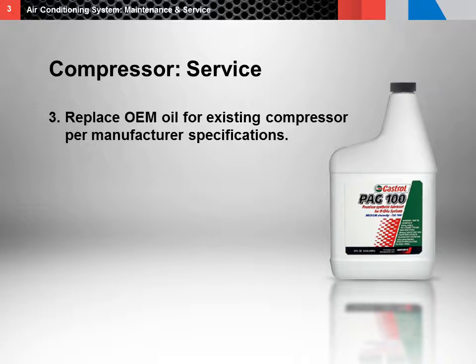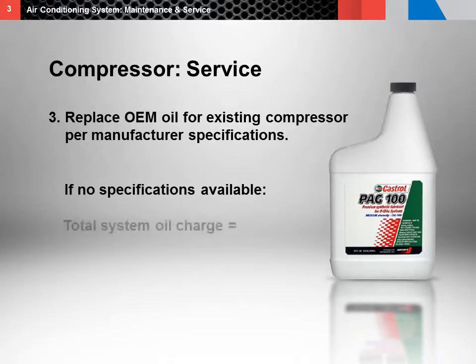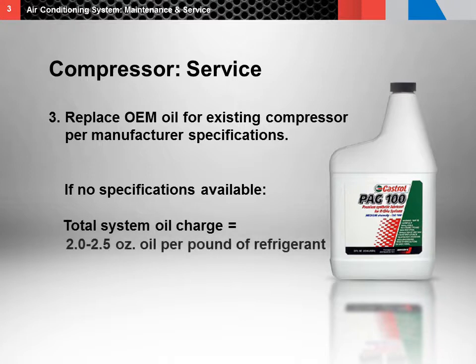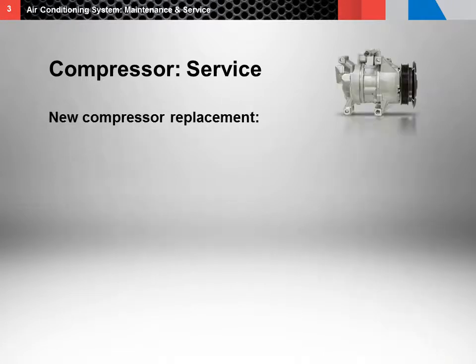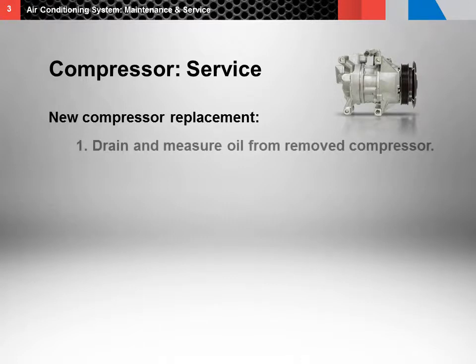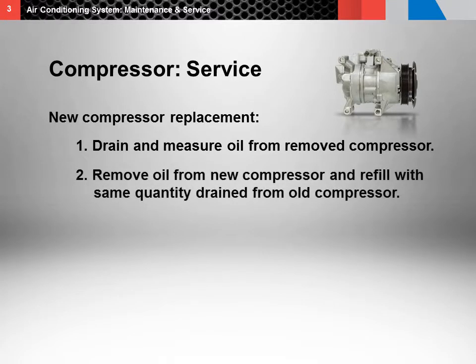The correct amount of oil to add should meet the OEM specifications. If there are no specifications available, the total oil system charge should be two to two and a half ounces for every pound of refrigerant in the system. When replacing an old compressor with a new one, drain and measure the oil from the removed compressor. Then remove the oil from the new compressor and refill the new compressor with the same quantity of oil drained from the old one.